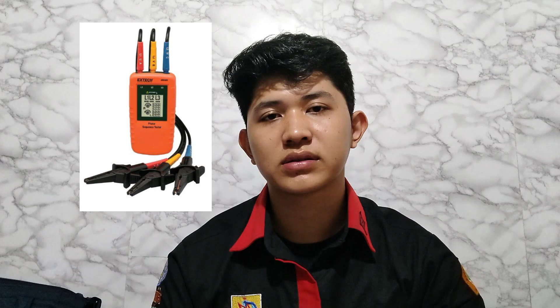If it's low, the insulation might be damaged. One more tool that is often used is the phase sequence tester. In a three-phase system, it is important to know the correct order of phases R, S, and T. If the sequence is incorrect, the motor can rotate in the wrong direction. The phase sequence tester helps identify the correct phase rotation before connecting equipment.